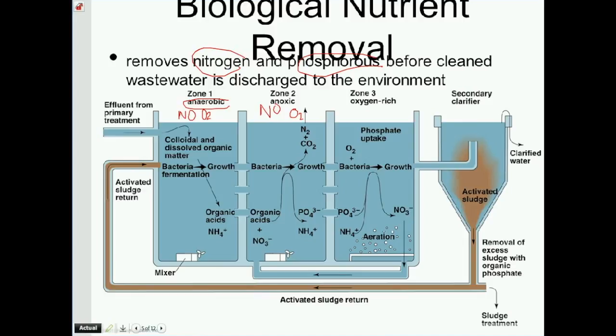So you've got these 2 anoxic areas where there's no oxygen, and you've got bacteria that does not need oxygen, feeding on all that sludge. And then you've got an oxygen area. It's oxygen rich, so we're going to have yes, O2. And then that's all going to go into this secondary clarifier tank. Okay, and it's going to get extra sludge out.